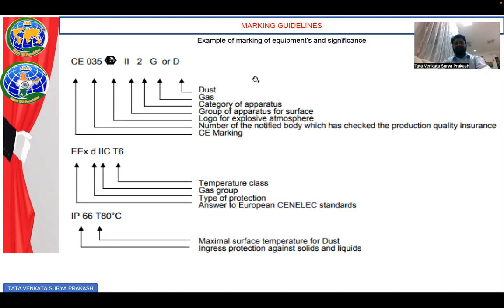And the type of protection, that is D class, the small d, is given there. So that is the type of protection required. And the gas group is 2C. The temperature class also should be mentioned. When temperature class 6 is mentioned, for example, it means 85 degrees or maybe 100 degrees. So when the operators know that this is designed for this temperature, it should not exceed the temperature. Accordingly we will design the temperature process conditions to meet those requirements. So these are all very important for us.